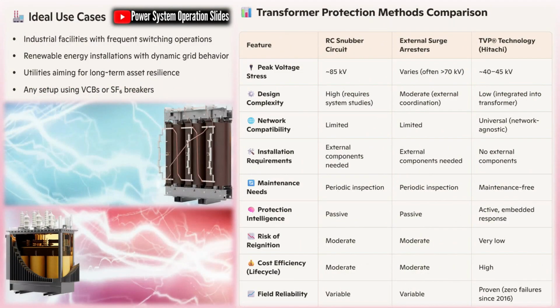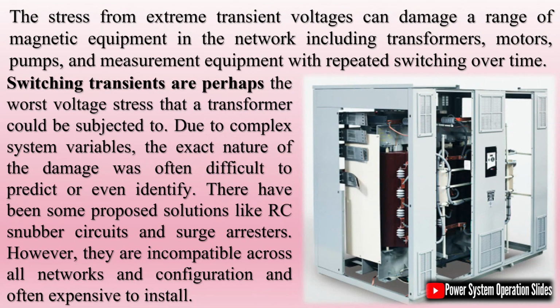Key feature: internal integration. TVP is built into the transformer, eliminating the need for external components. Real-time response: the varistors react instantly to voltage spikes, protecting insulation and windings. Maintenance-free. Once installed, TVP requires no additional servicing or monitoring. Network agnostic, effective across various grid configurations and switching environments.